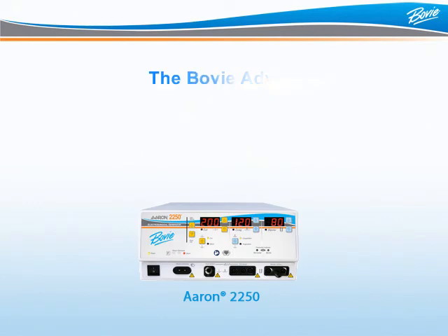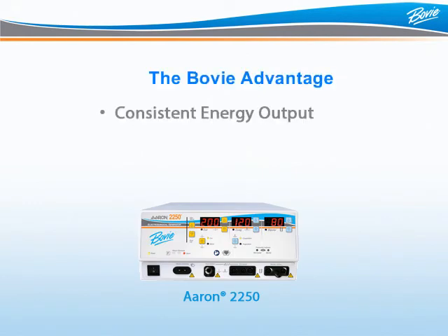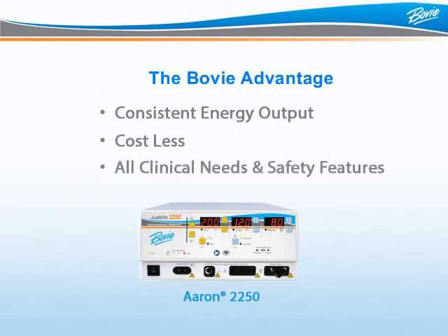From a clinical standpoint, none of the above competitors can match the consistent energy delivery of the Aaron 2250. This electrosurgical generator has technology that calculates impedance 5,000 times per second by sampling the current and voltage 5 million times per second. The Aaron 2250 is priced at least $2,000 less than its competitors, except the Hypersurge Op. ConMed's Hypersurge Op attempts to compete but leaves out important modalities — you can purchase the left-out mode for extra. The Aaron 2250 is the most cost-effective full-service ESU for the advanced physician office, surgery center, or OR with the same clinical effects and safety features of the more expensive hospital OR units.